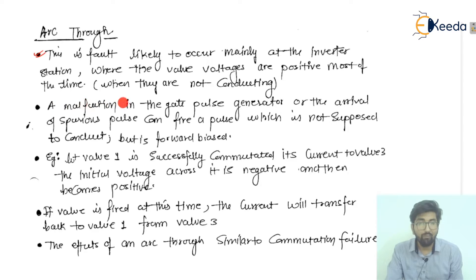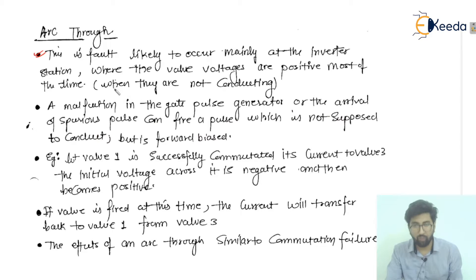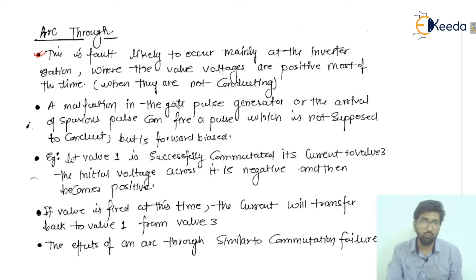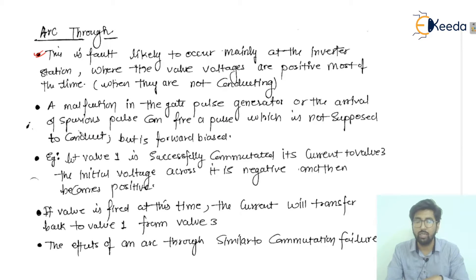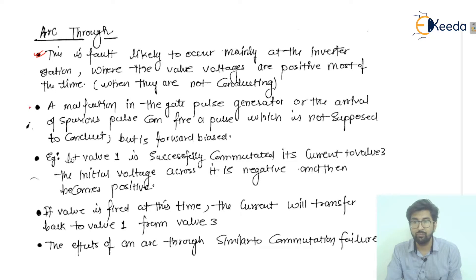A malfunction in the gate pulse generator, or the arrival of a spurious pulse, can fire a pulse to a valve which is not supposed to conduct. However, that valve is in a forward biased condition. So even though it is not supposed to conduct, because it is in the forward biased condition, it can be triggered into conduction.